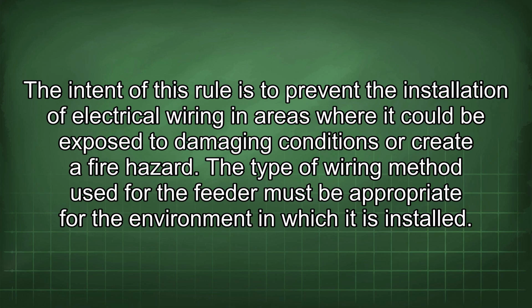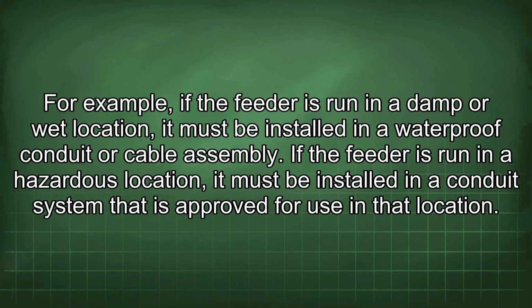The type of wiring method used for the feeder must be appropriate for the environment in which it is installed. For example, if the feeder is run in a damp or wet location, it must be installed in a waterproof conduit or cable assembly. If the feeder is run in a hazardous location, it must be installed in a conduit system that is approved for use in that location.